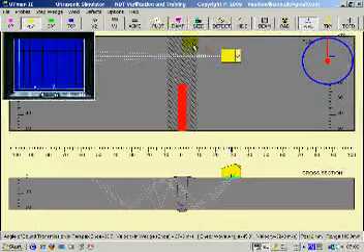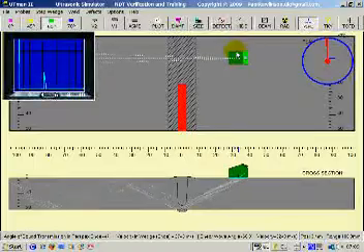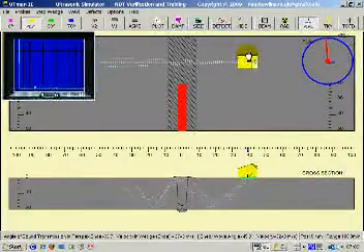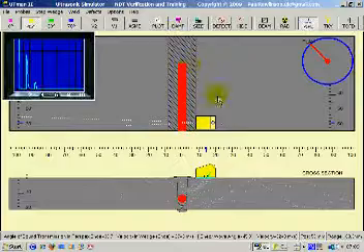If we're using a 45, we sometimes pick up, well, with any probe, we pick up what we call geometry. There is a good root signal. And we can see some of the cap signal here as well. With a 45 degree, we get a bigger cap signal. And if we rub the cap with our finger, then we can confirm that this is the cap.